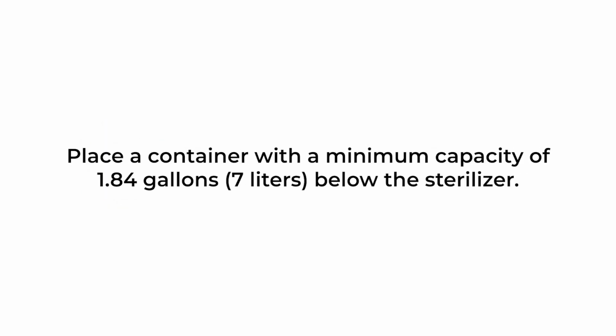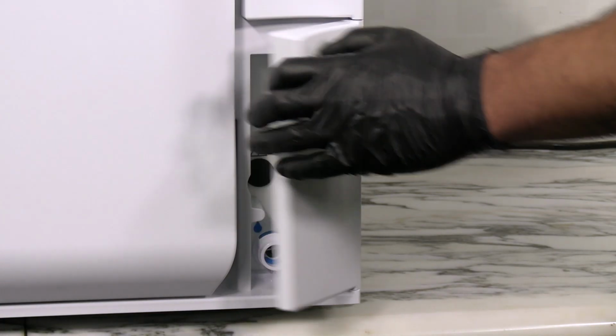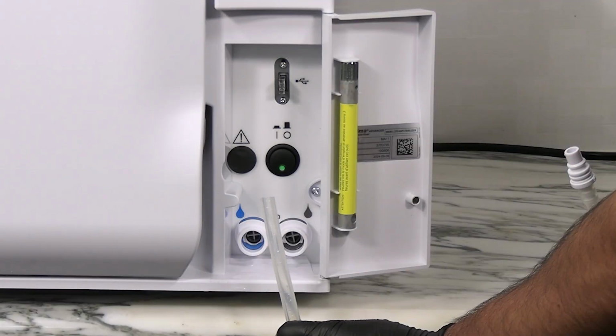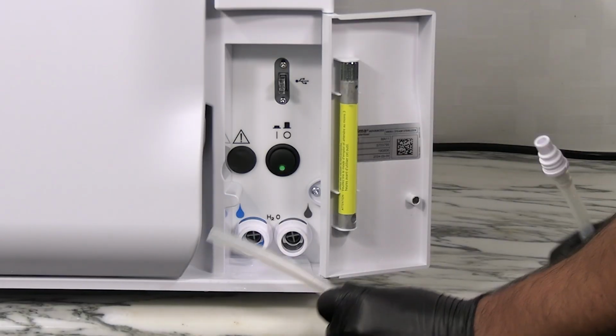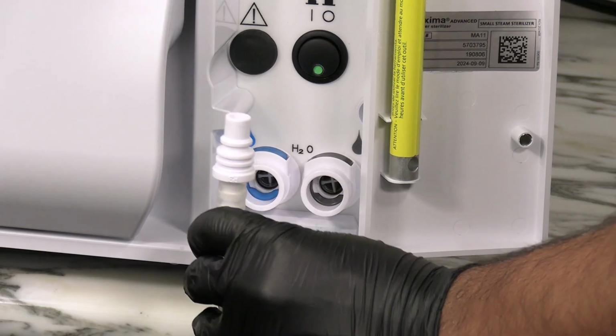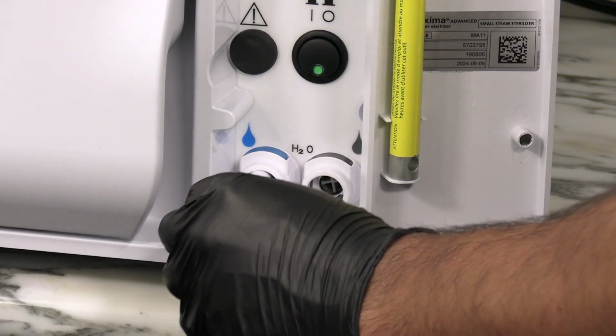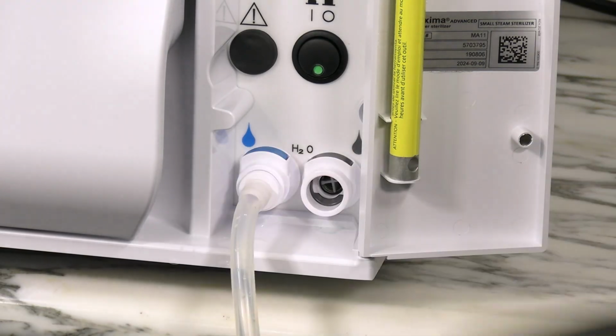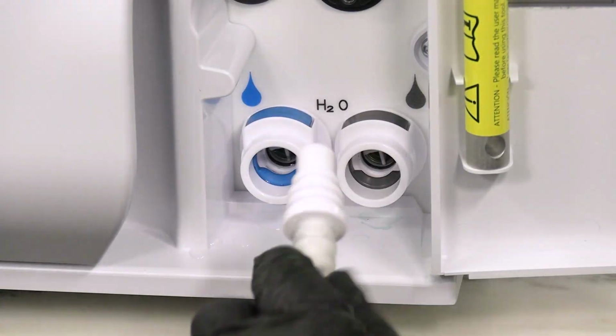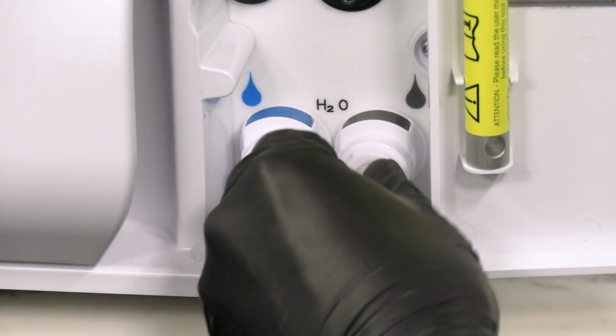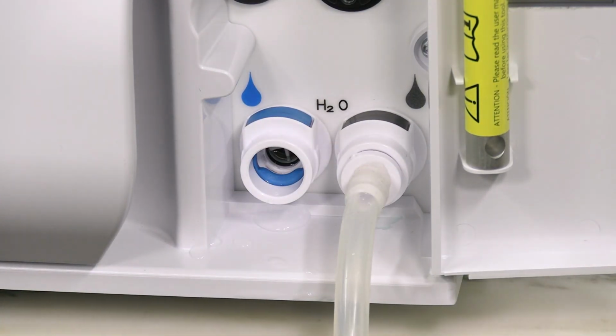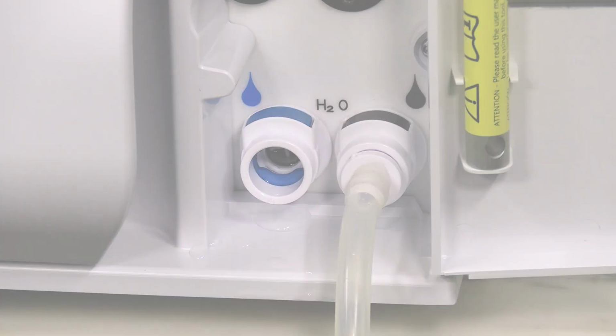Start by placing a container with a minimum capacity of 1.84 gallons below the sterilizer. Open the sterilizer service door. To drain the clean water tank, place one end of the drain tube into the container and firmly insert the other end into the blue drain connector. To drain the used water tank, place the end of the drain tube into the container and firmly insert the other end into the gray drain connector. Allow the water to drain completely from both tanks.